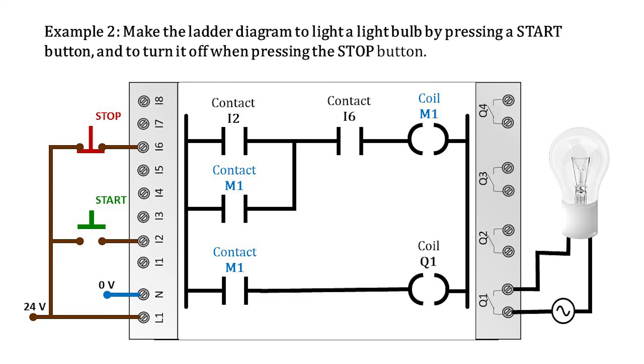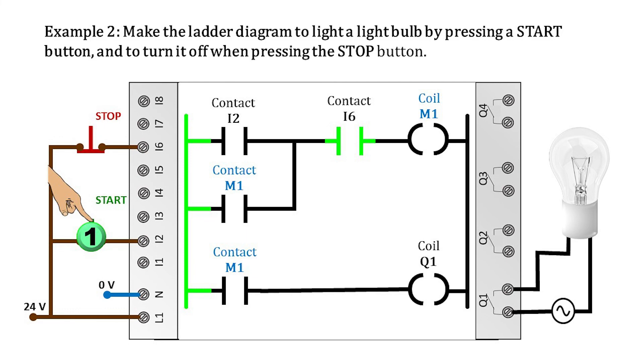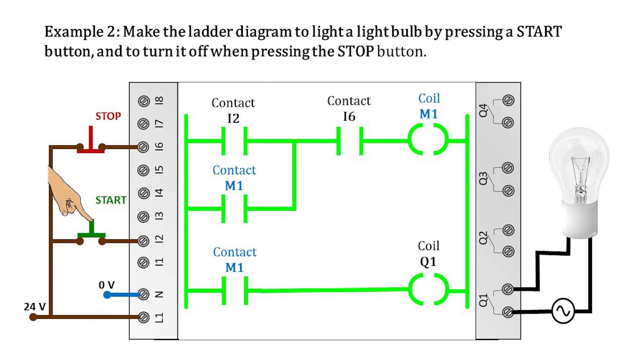When powering up the PLC or starting the simulation, each button will immediately send a signal to its respective input depending on the state they are in. In this case, the stop button sends a logic 1 to its respective I6 contact, causing it to change state — that is, it is activated. So these would be the initial conditions of the process. If we press the start button, it sends a high voltage level to input I2, which translates into a logical 1, activating the I2 contact. When contacts I2 and I6 are both active, coil M1 is also activated. The M1 coil sends a logical 1 to its respective contacts, interlocking the coil and activating the Q1 coil, which sends a signal to turn on the light bulb.